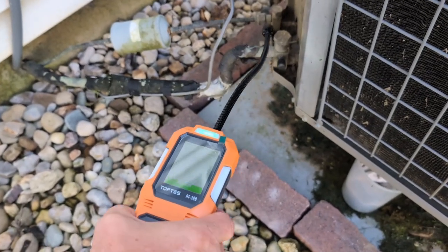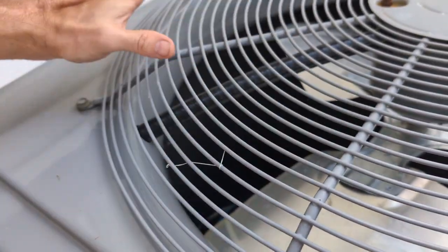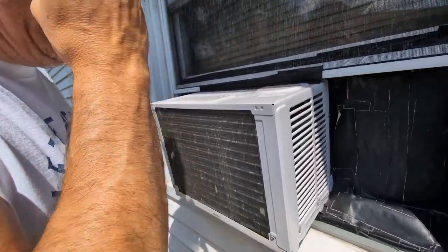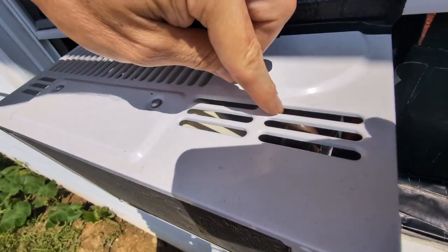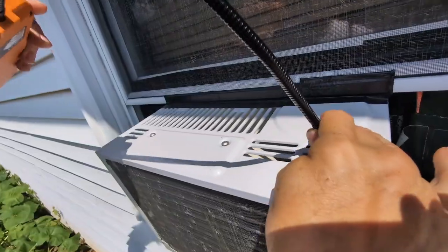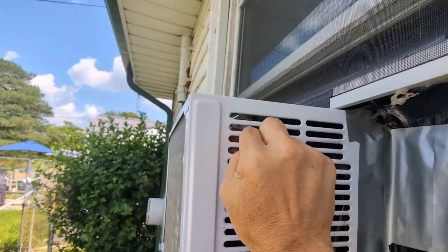We're just checking right here and there are no leaks. To properly check, you would have to take the lid off, take off the fan unit, and make sure it's powered down. Check the fan unit behind it and the coils if you want to check those. Out here is a small window air conditioner — right here there's sweat, that's actually the coil. You would check up in here. There is no leak here on this small window unit.